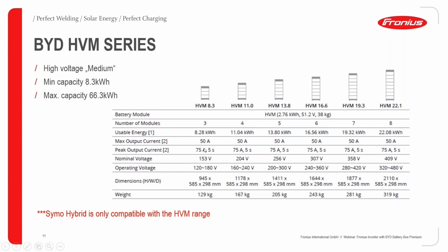Okay, so if we start off at this lower one, you'll have your current input of our inverter, which is 16 amps, times the nominal voltage, which will give you your power. I'll do some calculations on that later and you'll be able to see how to work it out. You can see here the voltage increases, starts at 153 and goes up to 409 with the biggest stack on there.